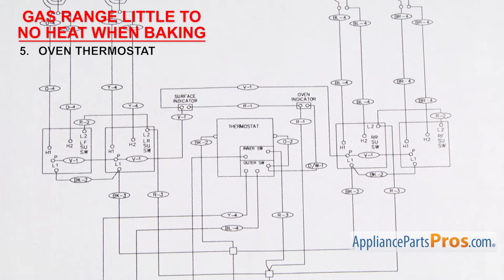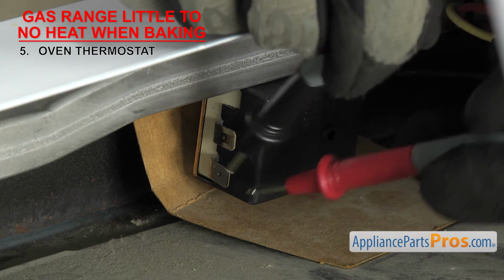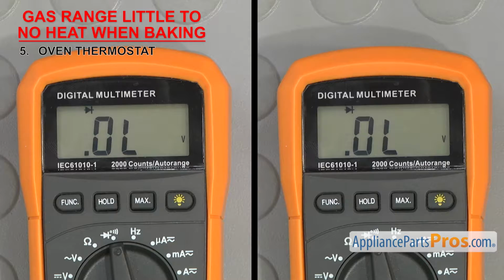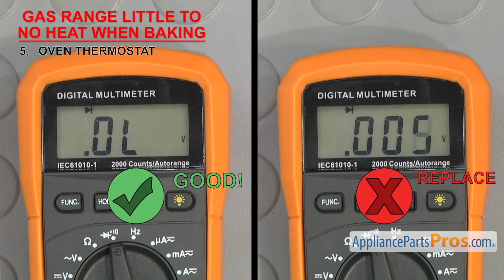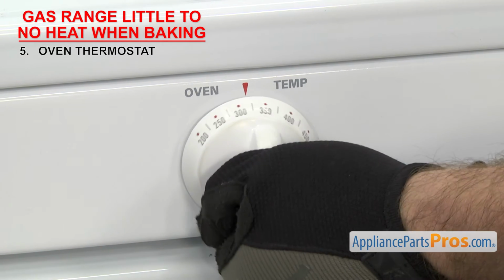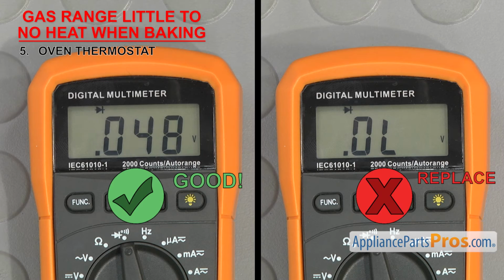bake and broil systems. Touch a probe to each terminal with the thermostat in the off position. It should not have continuity. Then turn the thermostat on. It should have continuity in the on position. If it fails either test or is damaged, it'll have to be replaced.